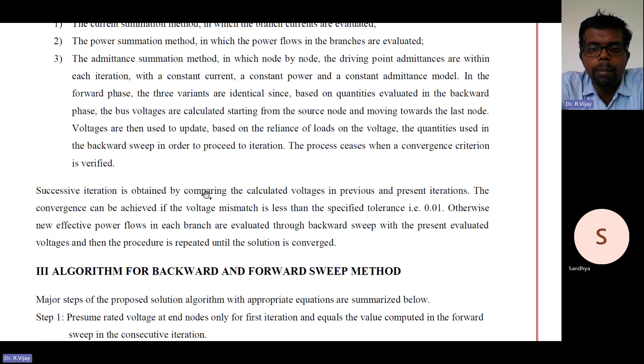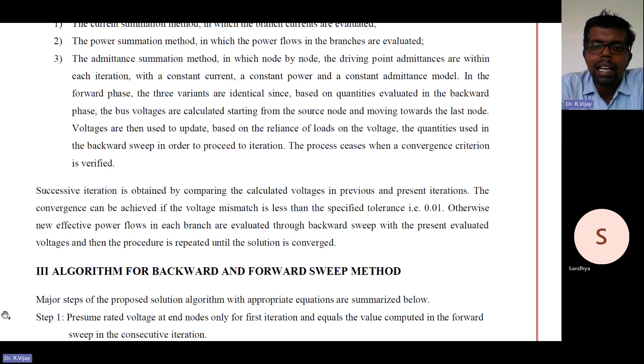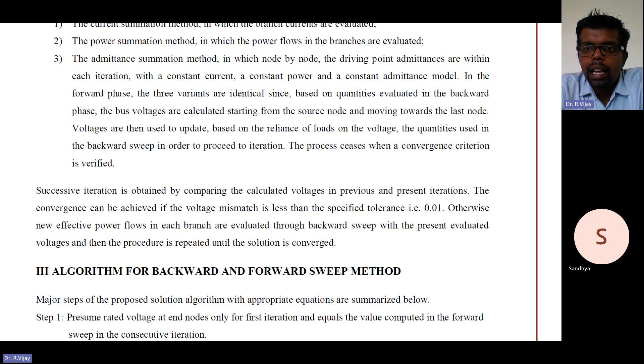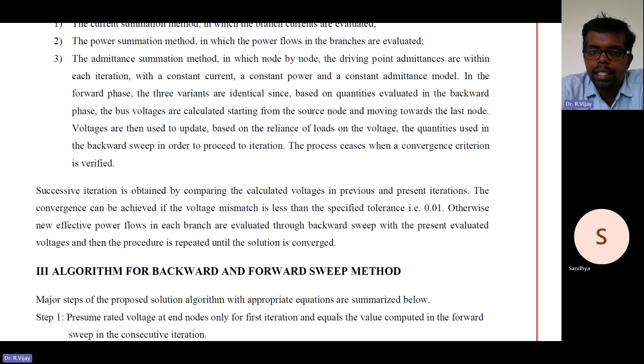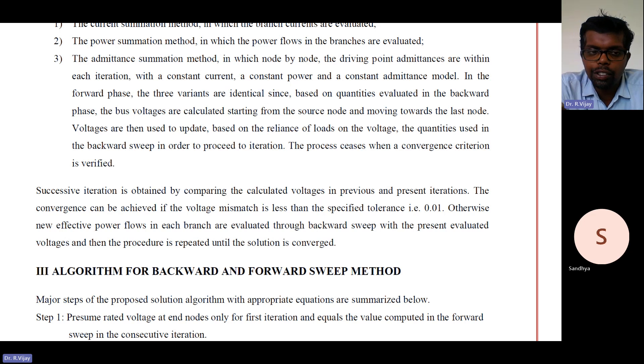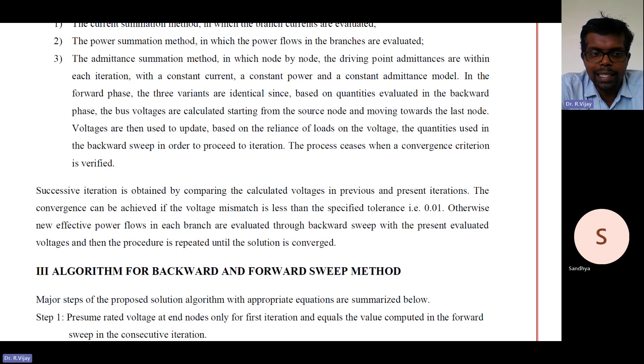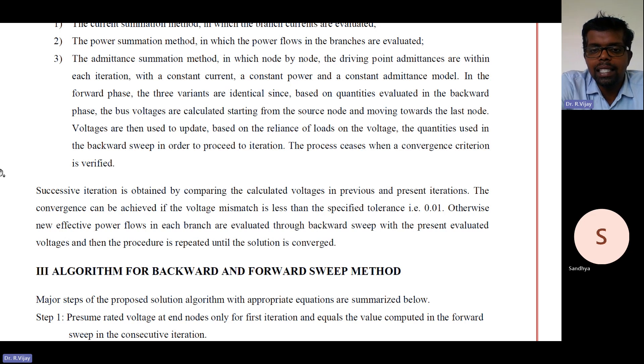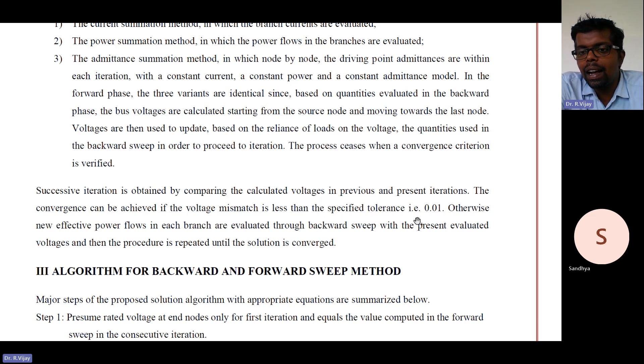Successive iterations are obtained by comparing the calculated voltage in the previous and present iteration. In the first iteration we get one voltage value, in the second iteration we get another, and so on. We compare successive iterations, and whichever iteration shows no significant change, we stop the iteration and print the results. Convergence is achieved if the voltage mismatch is less than the specified tolerance value, which is 0.01.